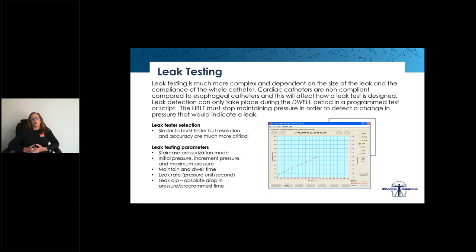Leak testing is more complex and is dependent on the size of the leak and the compliance of the whole catheter. For instance, a cardiac catheter is non-compliant compared to an esophageal catheter, and this is going to affect how our leak test is designed. Leak detection can only take place during the dwell period in a programmed test or script. The HBLT must stop maintaining pressure in order to detect a change in pressure that would indicate a leak. When we're selecting our leak tester, we want to consider similar things to our selection of a burst tester, but the resolution and accuracy are much more critical to leak testing.